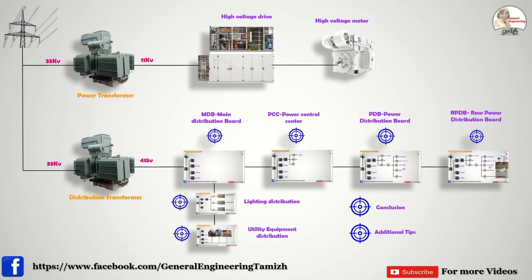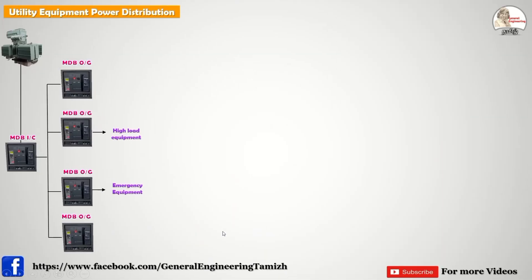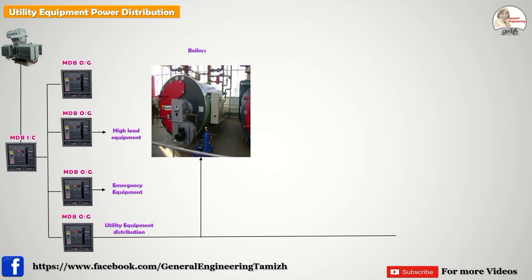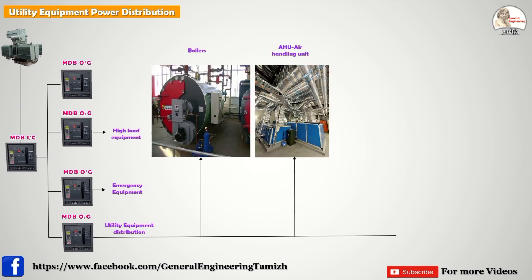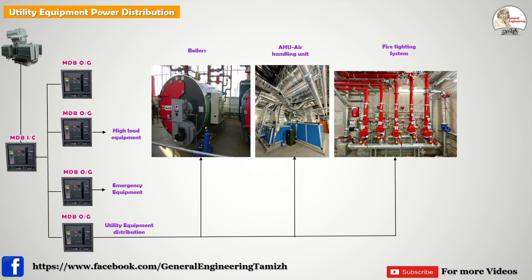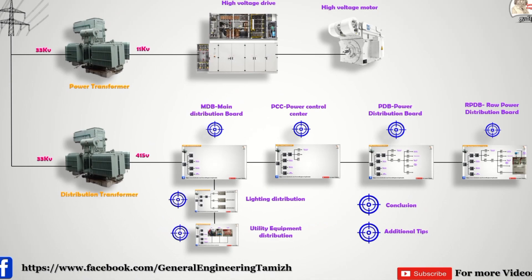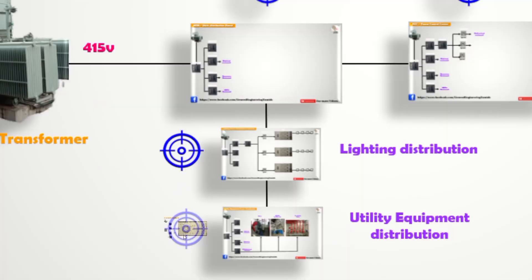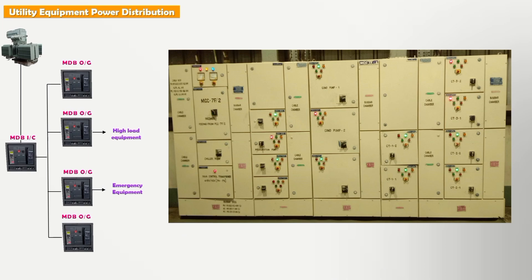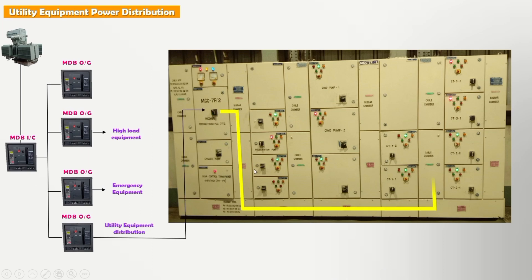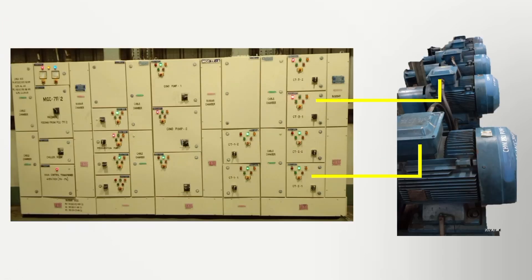Now lighting distribution is completed. Lastly, utility equipment must always be connected from the MDB with a separate distribution network. Utility equipment includes boilers, HVAC systems, building cooling systems, water treatment plants, and fire fighting systems. Utility panels are similar to PCC and PDB, but since utility equipment is mostly motors and pumps, the panels themselves maintain starters, and motors are connected from those starters.